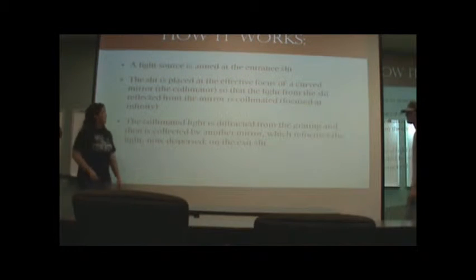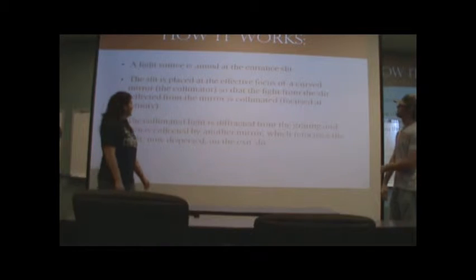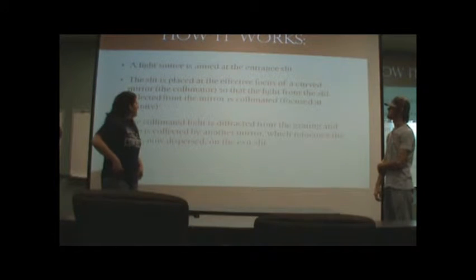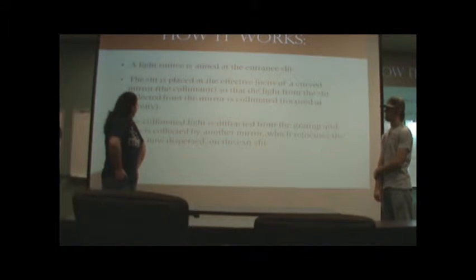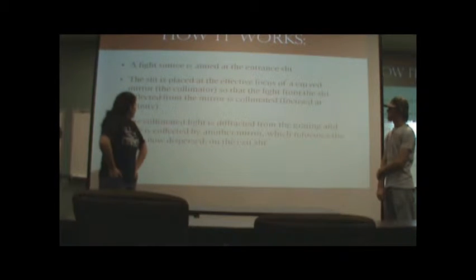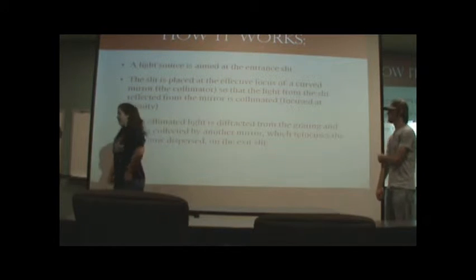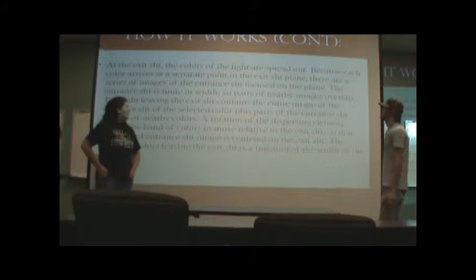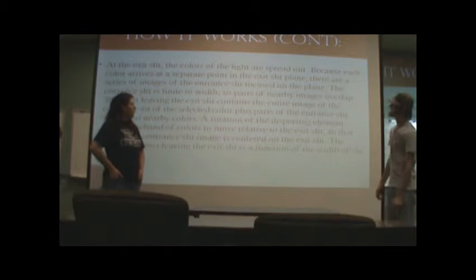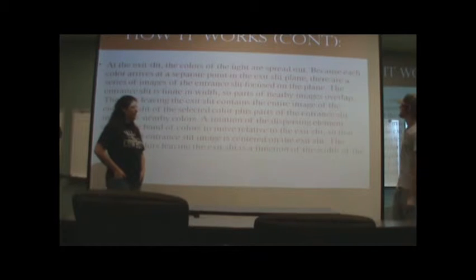A little bit more in detail about how it works. A light source is aimed at the entrance slit. The slit is placed at the effective focus of a curved mirror, which is the collimator, so that the light from the slit reflected from the mirror is collimated or focused at infinity. The collimated light is diffracted from the grating and then is collected by another mirror, which refocuses the light, now dispersed on the exit slit. And at the exit slit, the colors of the light are spread out because each color arrives at a separate point in the exit slit plane.